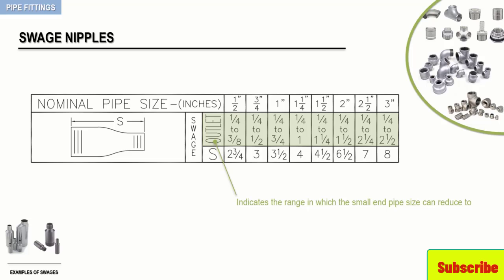Remember, all fittings attached after this swage are obviously of a smaller pipe size, and therefore will not only be shorter in length, but will also have a shorter thread engagement. These important factors should not be overlooked when calculating the center-to-center dimensions of screwed or socket-weld configurations. We will see this in detail further ahead.